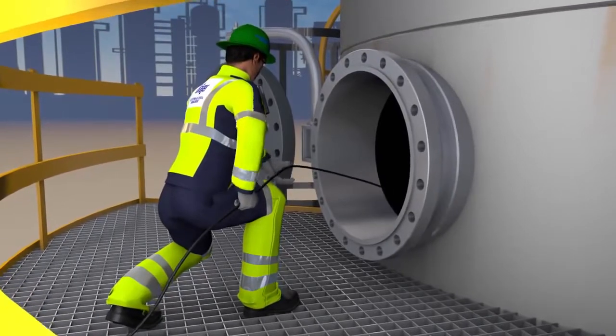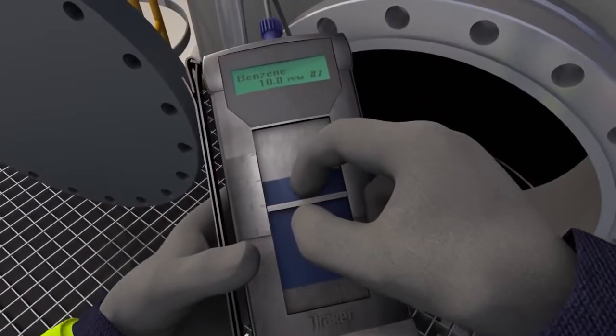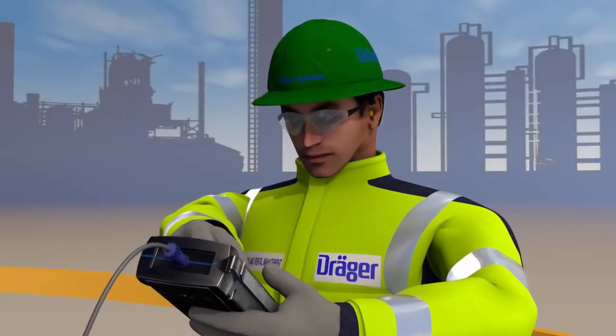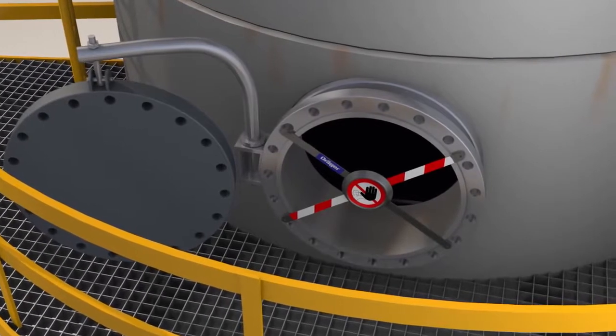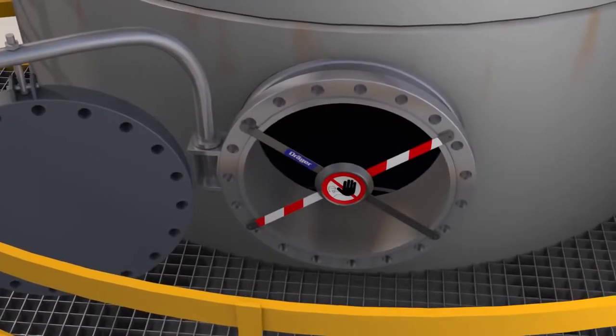Based on the individual circumstances on site, another measurement is performed according to the measurement strategy. This time, the Gas Analyst uses the Dräger chip measurement system CMS. With this instrument, he can conduct substance-specific measurements, and it is precisely during this measurement that the device flags up a relevant reading. At 10 ppm, the benzene content where this crew is working is too high. The Dräger Gas Analyst cordons off the area and initiates additional steps.